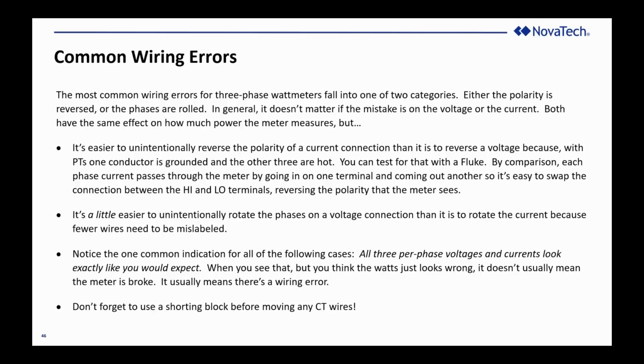And if you reverse the connection of those two terminals, you would invert the polarity. It's harder to do that with the voltage because one of the three conductors is ground and the other three conductors are hot. It's very easy to see which one's neutral with a handheld Fluke. It's not as obvious which one's A, which one's B, and which one's C, so it's very easy to rotate the phases on the voltage.